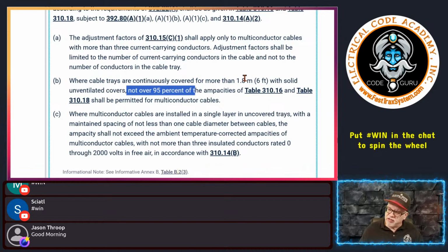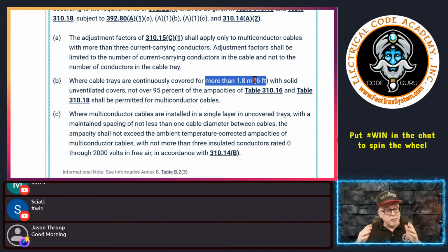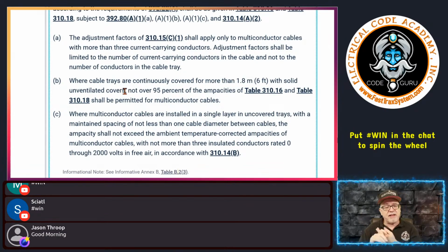But if you look here, this just says more than 6. So it could be 20 feet, could be 30 feet of covered, I don't know. And obviously, if that's the case, then 310.14(A)(2) and the subsequent exception, it's probably not going to help you any. But I always like to point those things out for the design professionals because it may save your day.